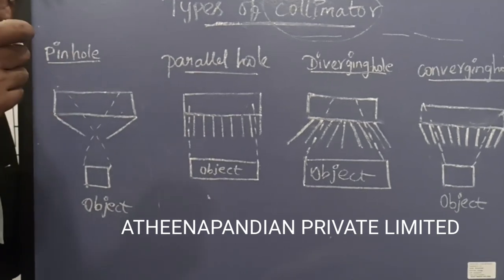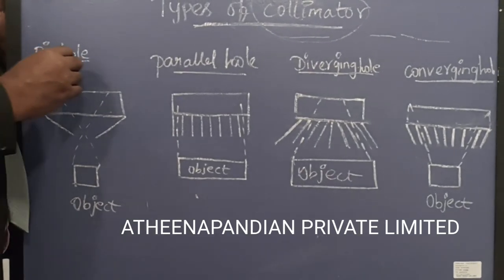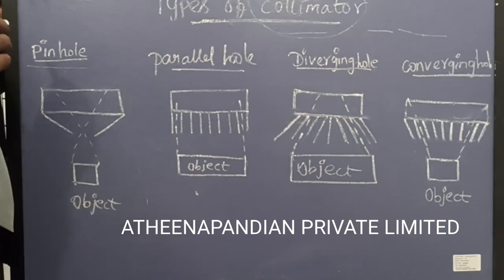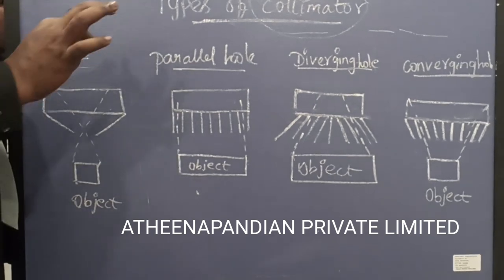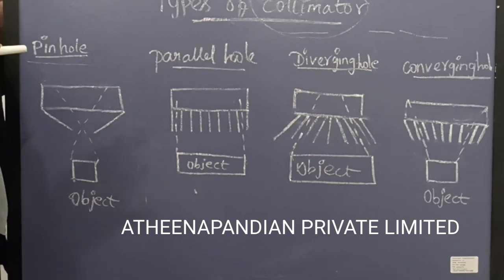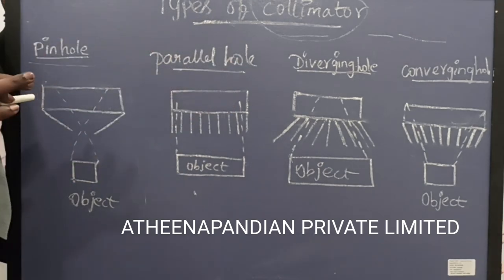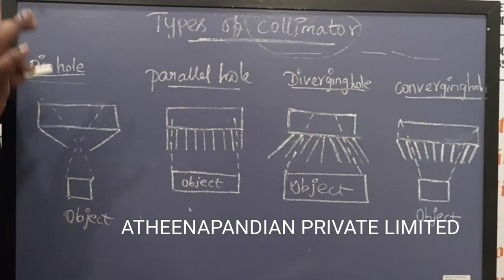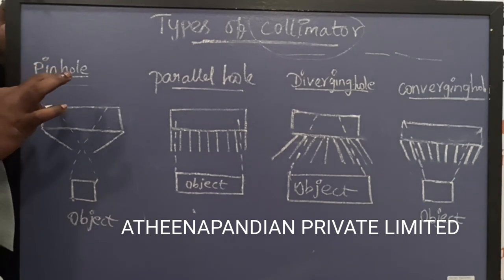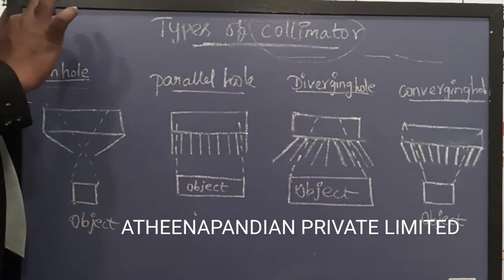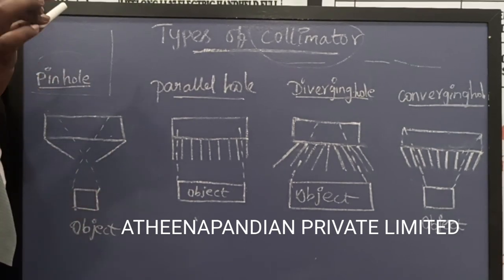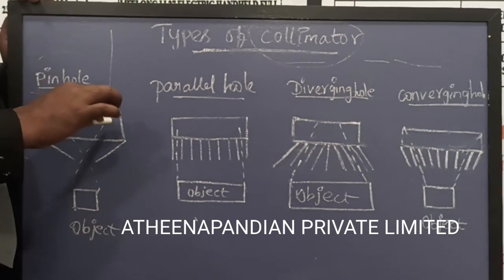There are four different types of collimator actually used in the medical field: one is pinhole collimator, parallel hole collimator, divergent collimator, and convergent collimator. You must understand — the name itself shows what it does. It is very simple actually. According to the name, you can see the diagrams and clearly understand the purpose of each collimator. If you want a single dimensional source for a small area of depth, we can use the pinhole collimator.